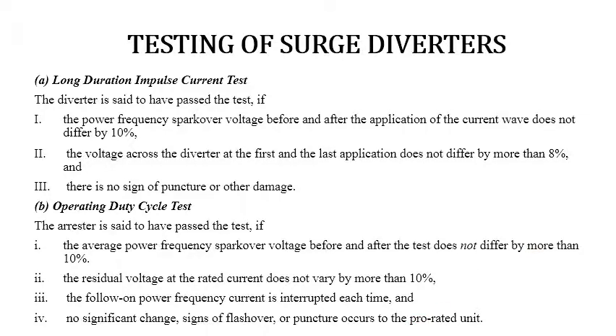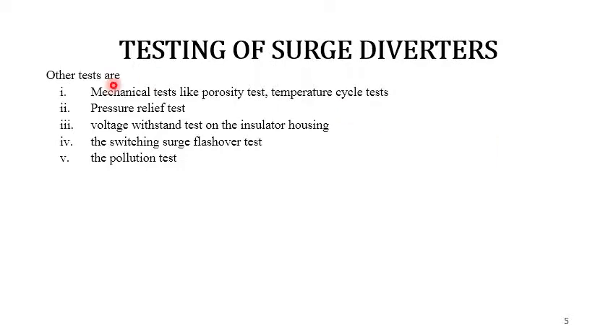Other than this, we have other tests, that is, mechanical tests like the porosity test and temperature cycle test, then the pressure relief test, then the voltage withstand test on the insulator housing, then the switching surge flashover test, and then the pollution test. These tests are usually done on diverters which are used in EHV systems.